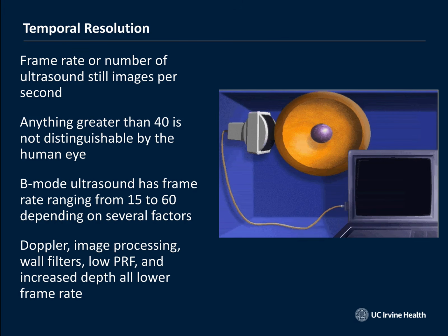But those images tend to be a little grainier because you're turning off all the other image processing in order to get the highest possible frame rate. When you work with abdominal software settings, you do have lower frame rates, sometimes as low as 15, without even activating the Doppler. But the image looks beautiful because it's scraping off all the artifacts and processing the image, so things look really pretty on the screen, not grainy. So what happens when you activate the Doppler?